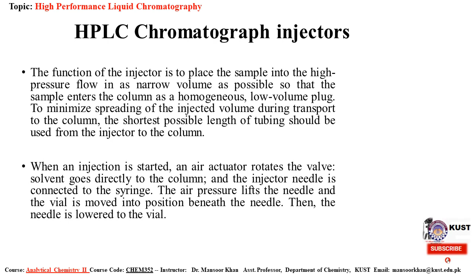When an injection is started, an air actuator rotates the valve. Solvent goes directly to the column and the injector needle is connected to the syringe. The air pressure lifts the needle and the vial is moved into position beneath the needle. Then the needle is lowered into the vial. This explanation basically describes a valve injection system, where a proper amount of the sample is injected into the valve injector by using a syringe. After that, the valve is returned and the mobile phase comes into the injector, where the sample is placed, and it takes it into the column for separation.